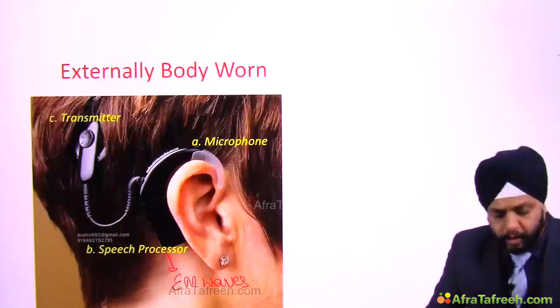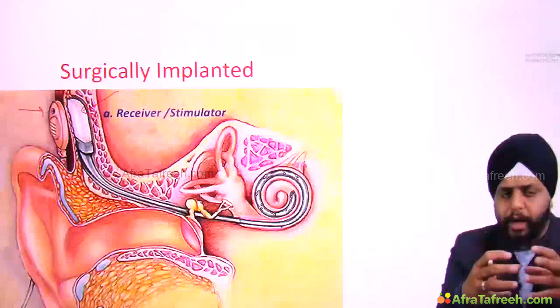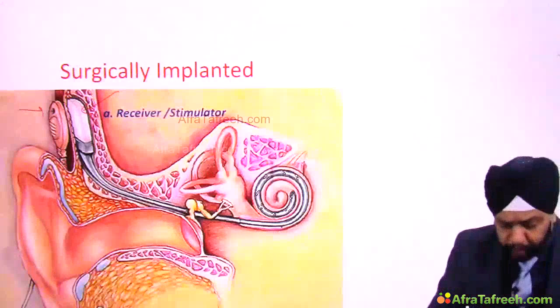Let's look at the surgical implantable part, the second part of the cochlear implant. So we can see that this part, the surgically implanted part, has a receiver stimulator. Okay, so on this receiver stimulator, the transmitter is attached by a magnetic effect. Okay, so there's a magnet. So with the help of the magnet, this transmitter is attached to this receiver stimulator, which is surgically implanted below the skin, right? And the second part of the surgically implantable device is the electrode array. So this electrode array goes inside the cochlea. Okay, which part of cochlea? The scala tympani.